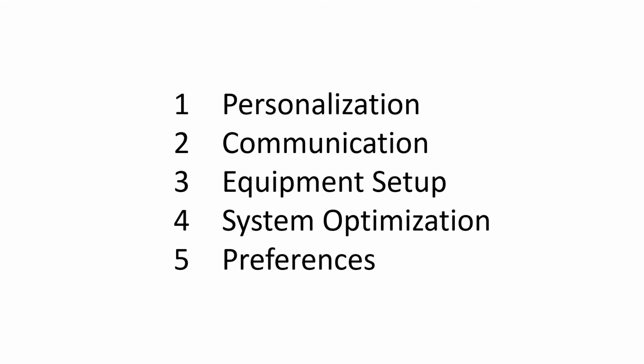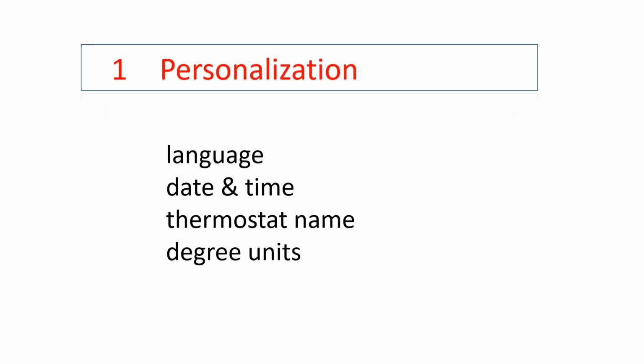We'll go to the bottom 4 times, we'll enter full setup, and we'll see 1 through 5 on the screen. Personalization, communication, equipment setup, system optimization, and our preferences. The personalization is where we have the language, date and time, thermostat name and degree, Fahrenheit or Celsius. Remember, the date and time will be automatically set by the Wi-Fi. So if you skip this section, you can use the default name. It will default to Fahrenheit and default to English for the language.